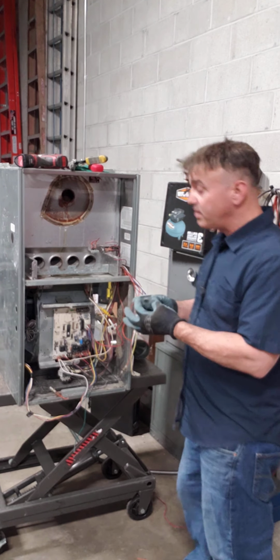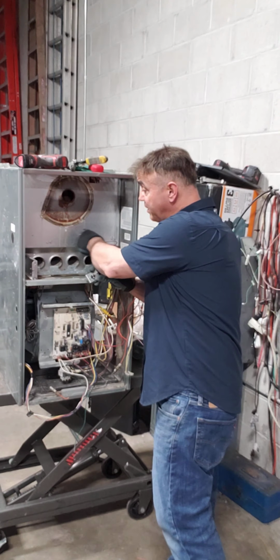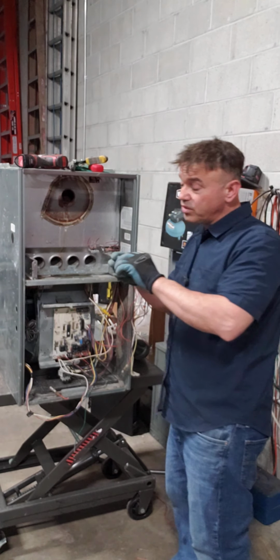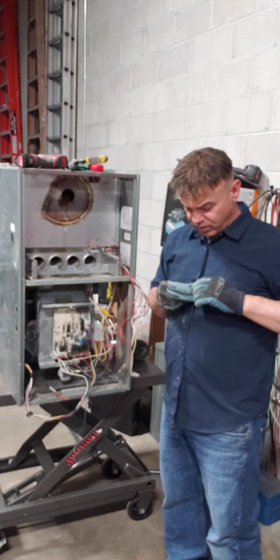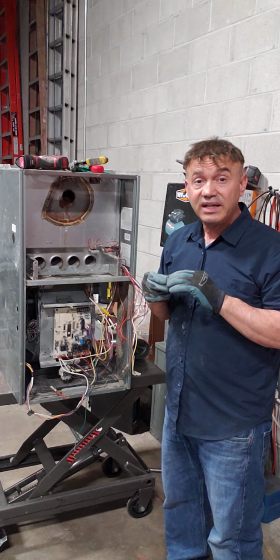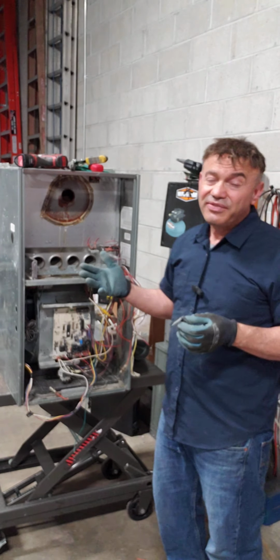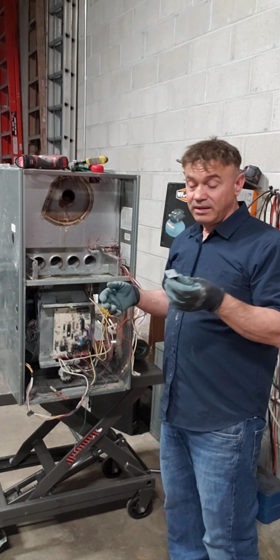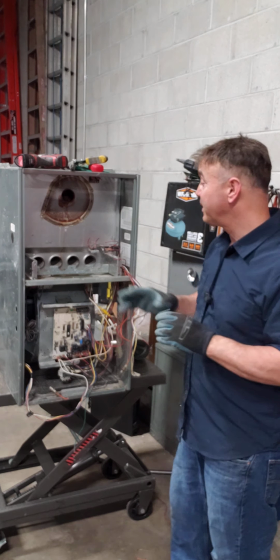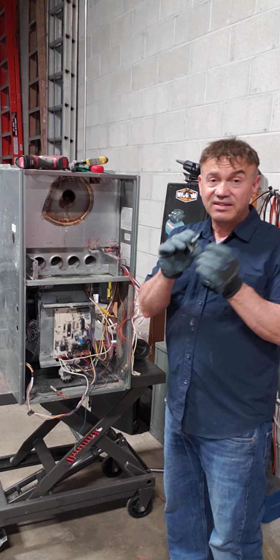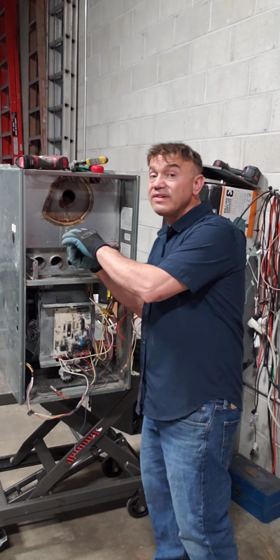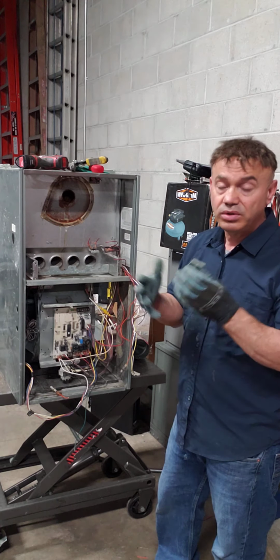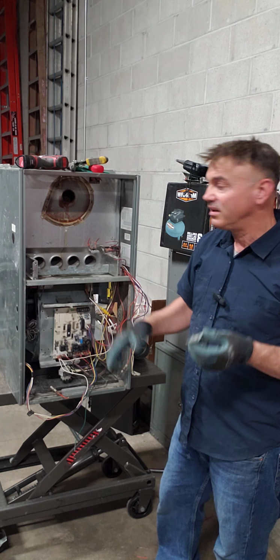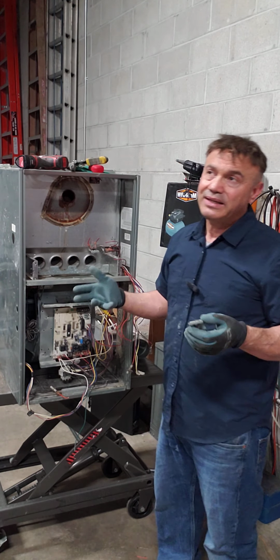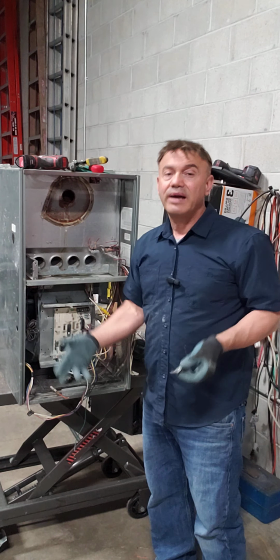So this is the rollout switch. Now if you go to your furnace and you have no heat, there are three of them here, and another one here. If you touch it and feel it click like this, that means 95% it's not this guy - he's just doing his job. There's a 5% chance this is bad. You can reset it; if it works afterward with no more problems, it was just a one-time thing. But if you reset it and it happens again, in 95% of cases it will keep happening.